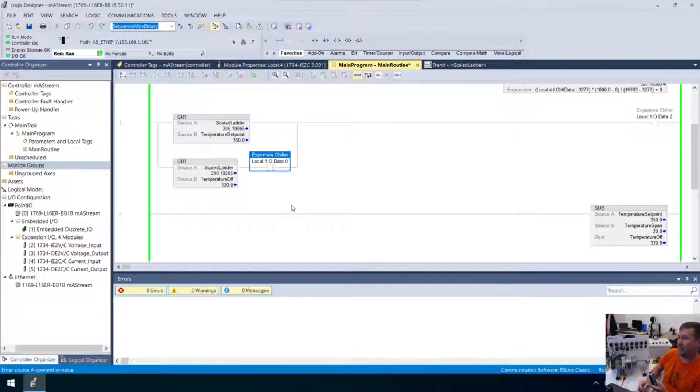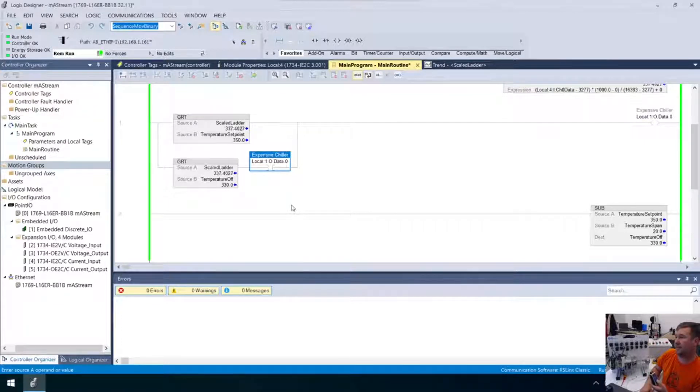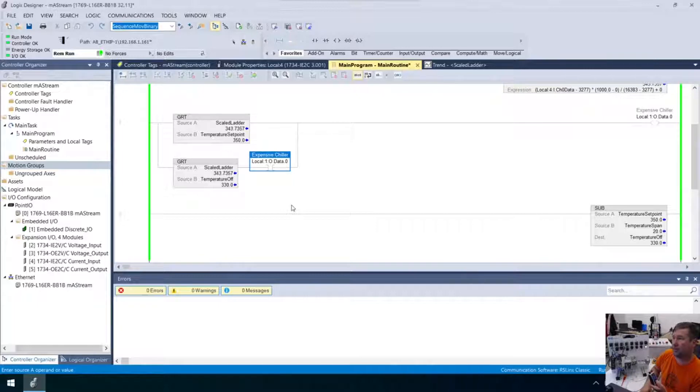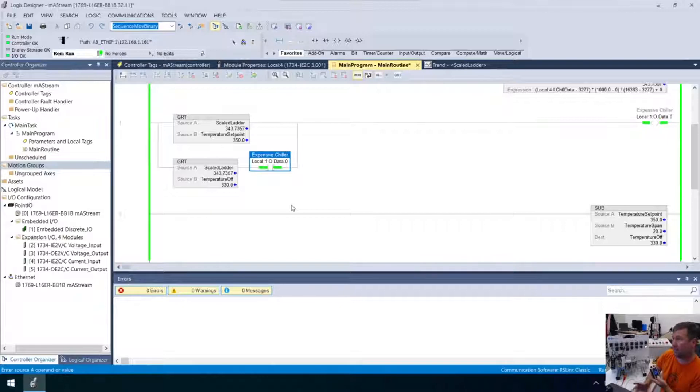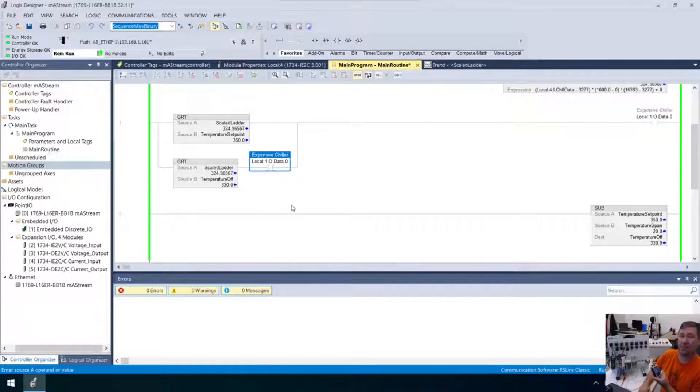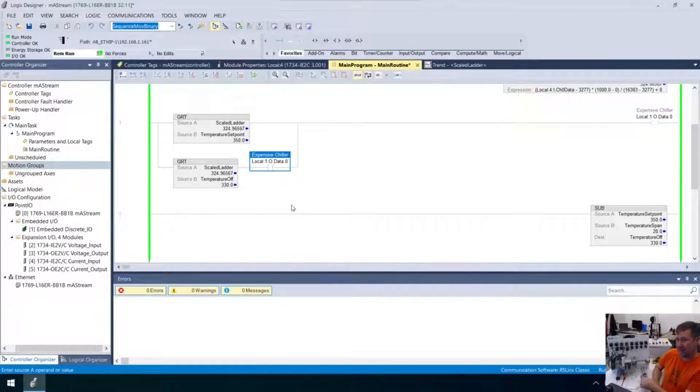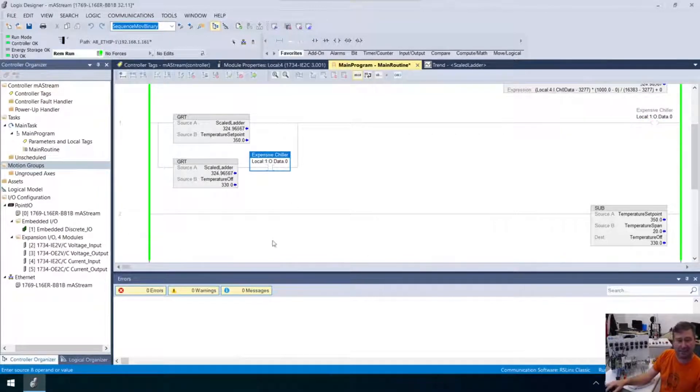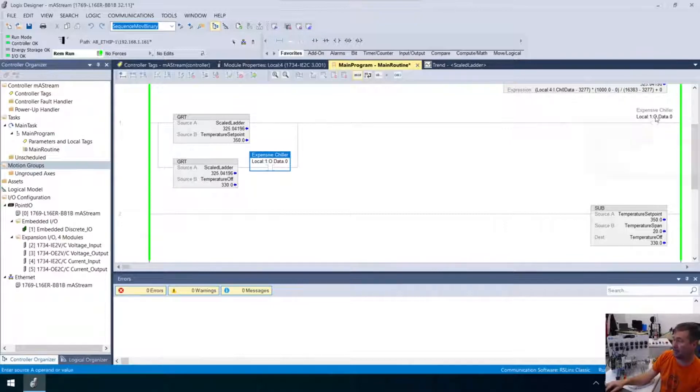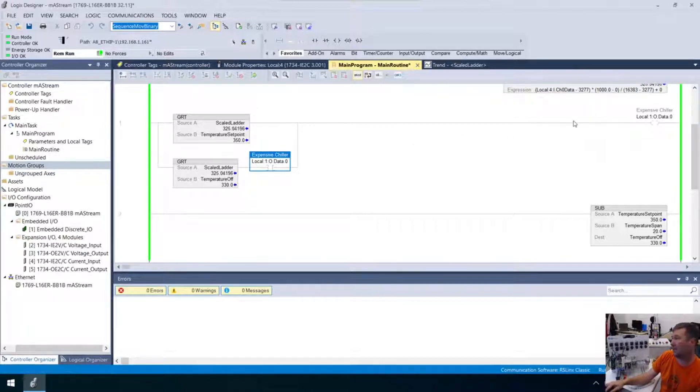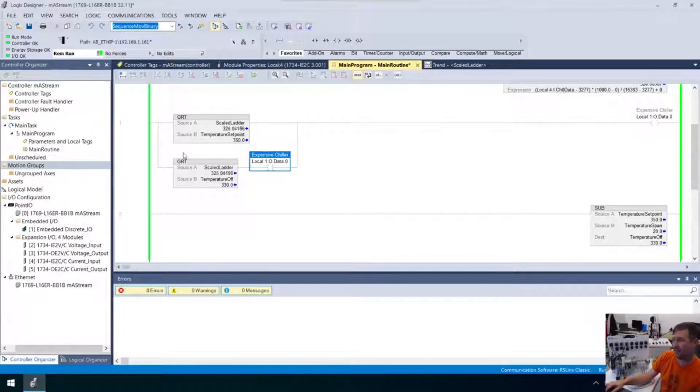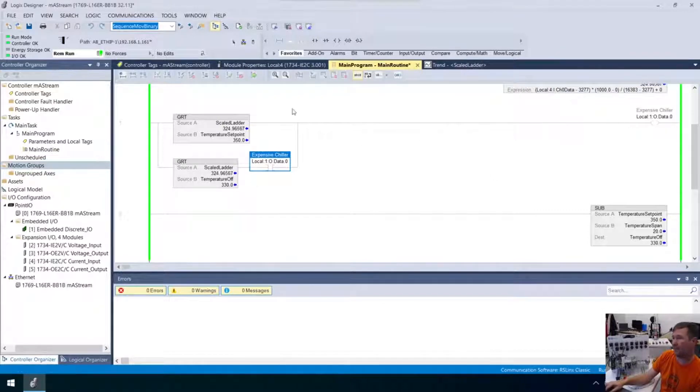Now, so what we got to do is we got to figure out a span that one is going to be acceptable to the customer, but also it's going to save our equipment. Because right now we're hammering this thing on and off. And the less on and off transitions we can make, the longer our equipment's going to last. So we want to go here. And for now, I'm just going to throw 20 in here again, just so we can kind of see that what's happening. All right. So now let's look at this. So this is 350. We already saw this is occasionally dropping to 349. So this greater than is going one zero, one zero, one zero, which is changing this beforehand. But now we have our lower branch again. And now if it's greater than 330, this bottom greater than is going to be true.